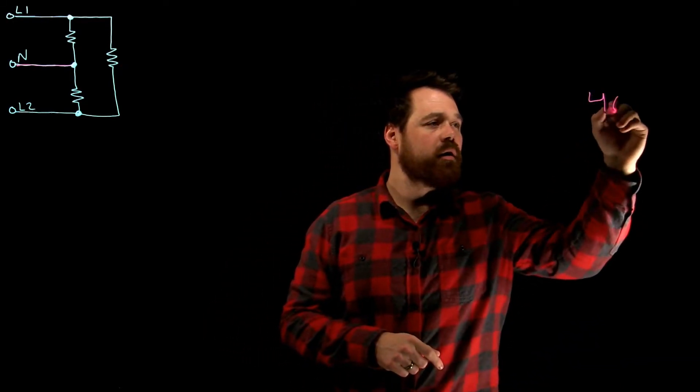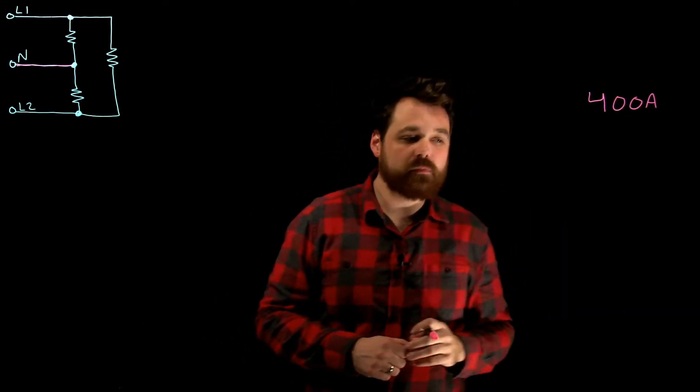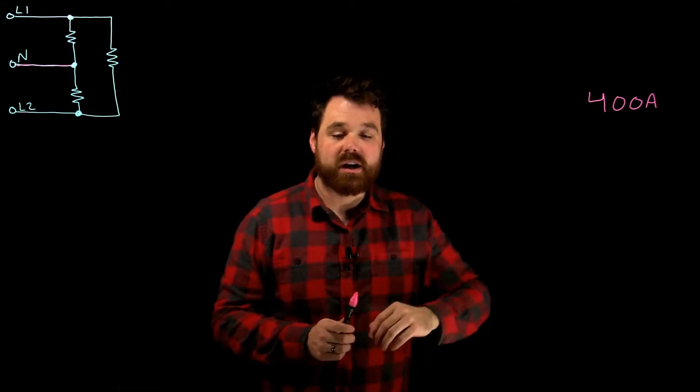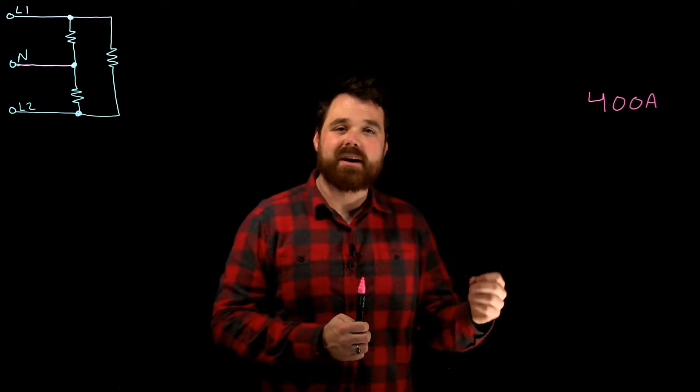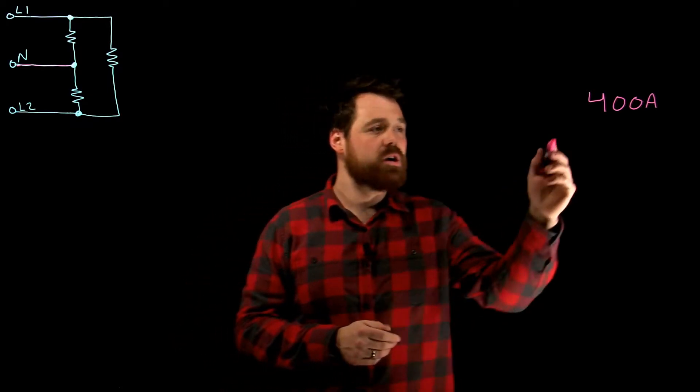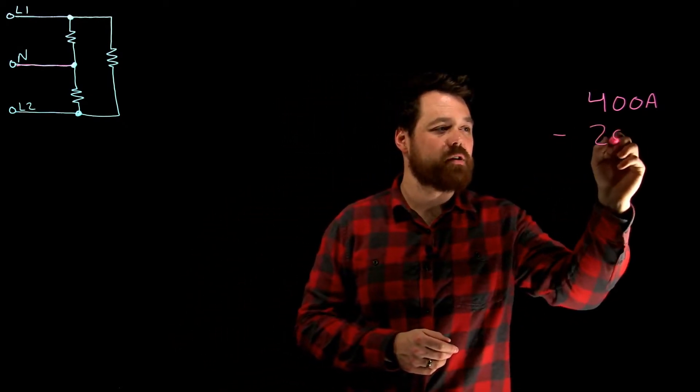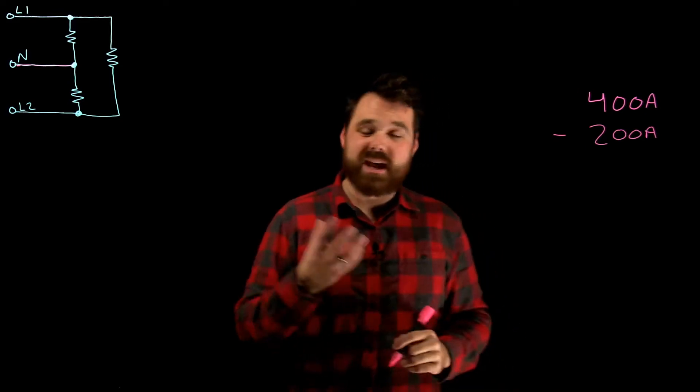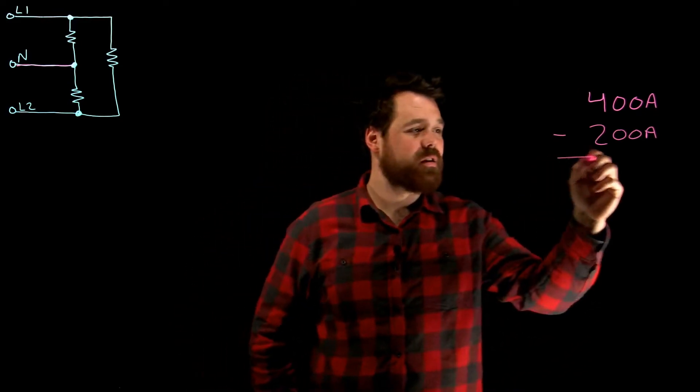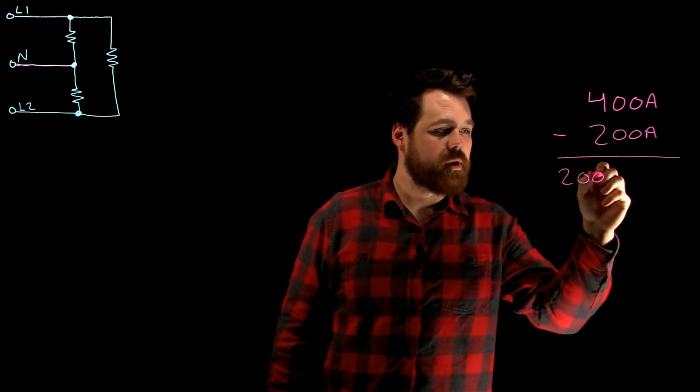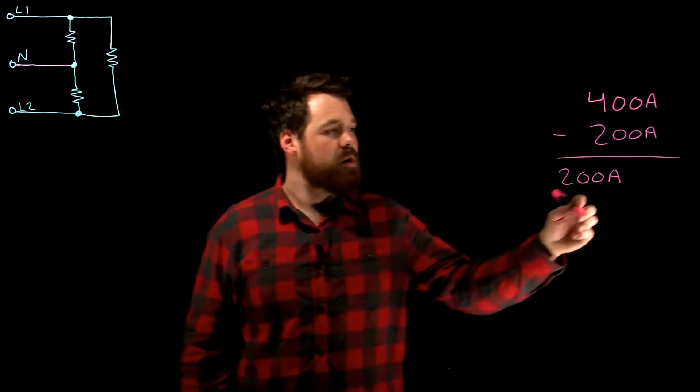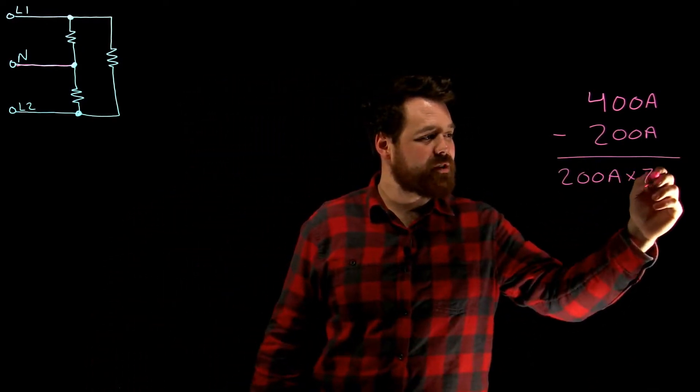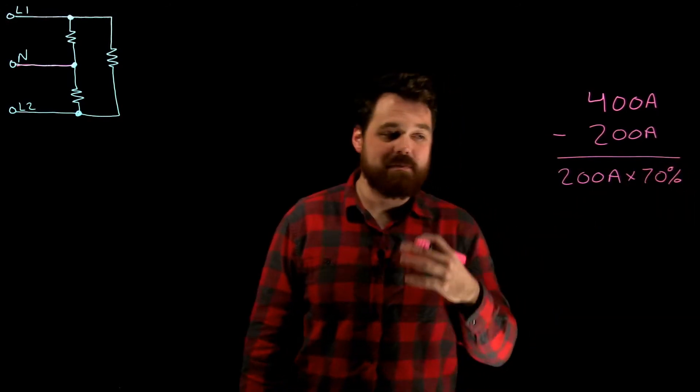If we had 400 amps, what it tells us is other than the first 200 amps you can apply a demand factor of 70%. So what we need to do is we need to minus that 200 amps because we cannot apply a demand factor to that, which gives us a remainder of in this case 200 amps, not always going to be 200 amps.